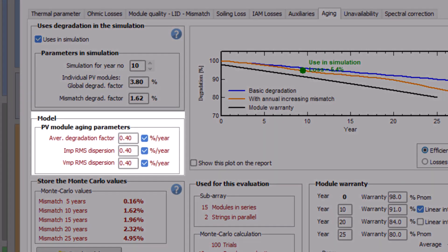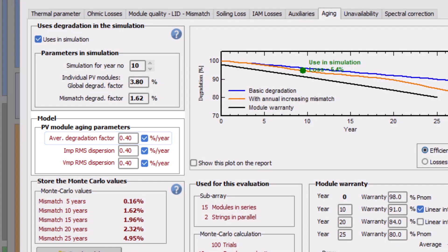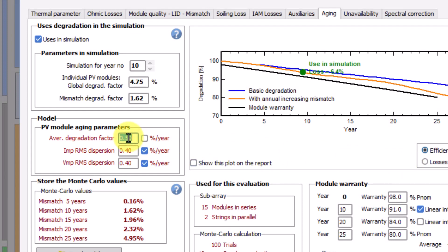In the Model section, you can define the PV module aging parameter per year. The first value is the average degradation factor of the PV module. This parameter is the annual average factor of the aging rate of the module. Typically, a consistent degradation rate for silicon technology is around 0.3 to 0.5% per year. In this example, we shall fix the value at 0.5% per year.